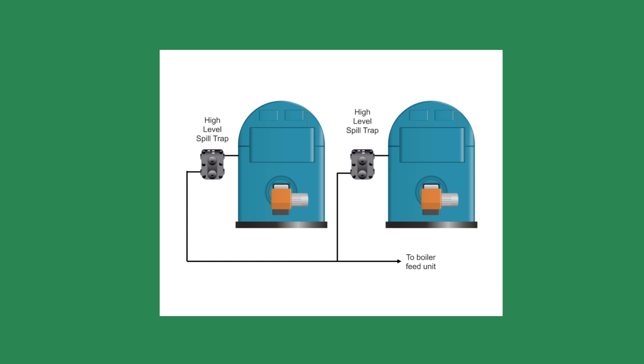The way to repair this situation is to install high level spill traps. After explaining the situation and showing them the boiler code, they agreed to the work.